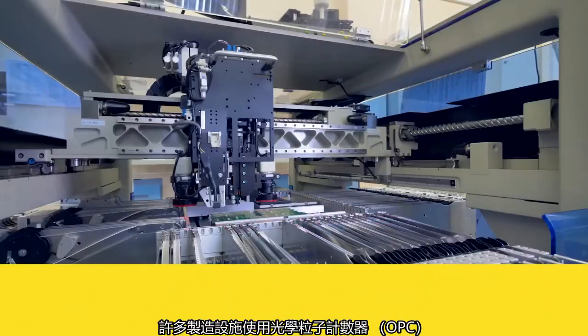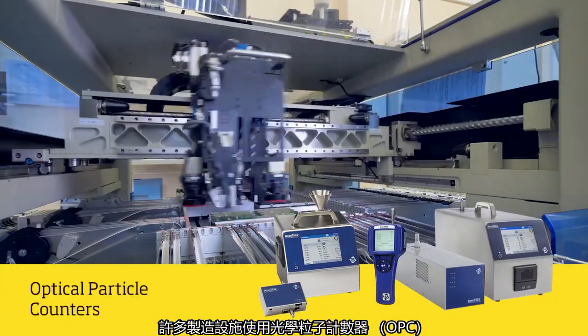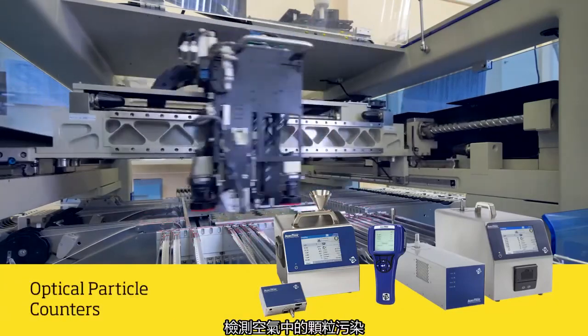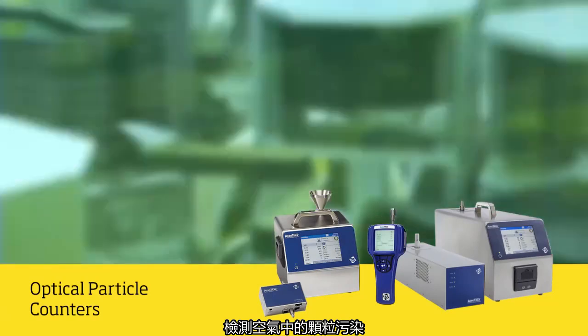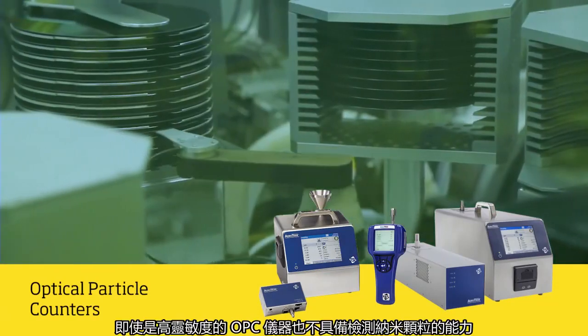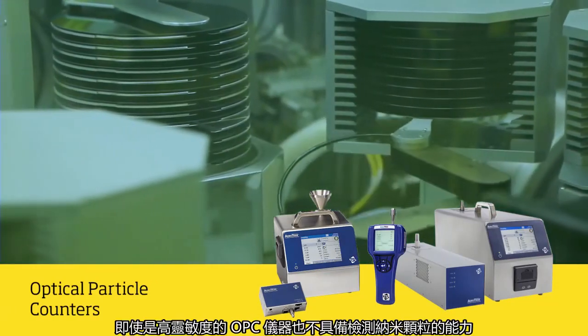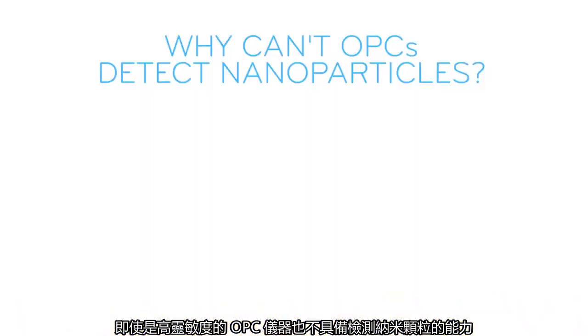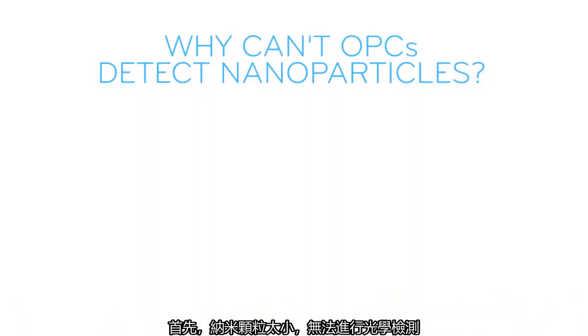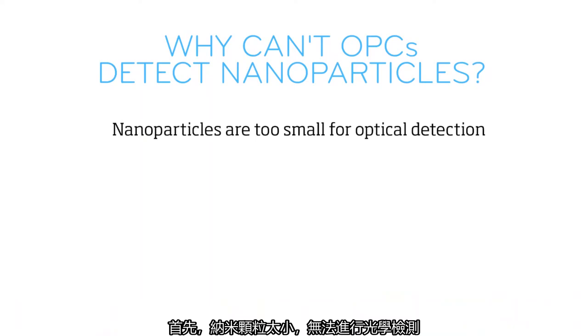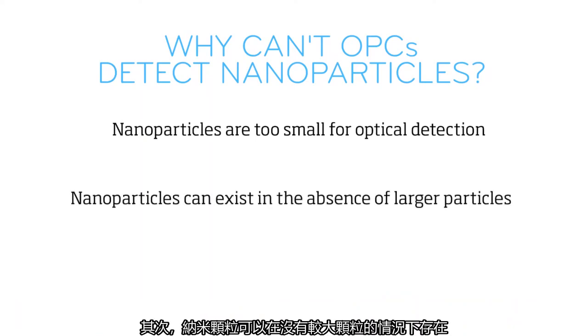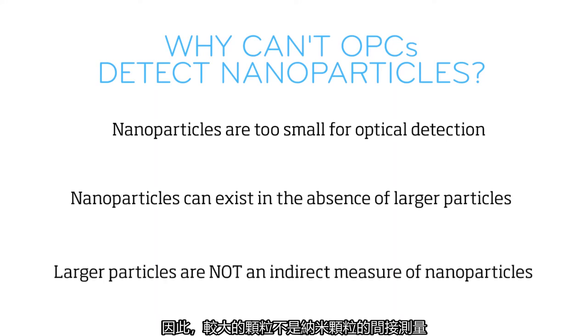Many manufacturing facilities use optical particle counters, or OPCs, to detect airborne particle contamination. However, even highly sensitive OPC instruments do not have the ability to detect nanoparticles. Why is this? First, nanoparticles are too small for optical detection. Second, nanoparticles can exist in the absence of larger particles. Therefore, larger particles are not an indirect measure of nanoparticles.